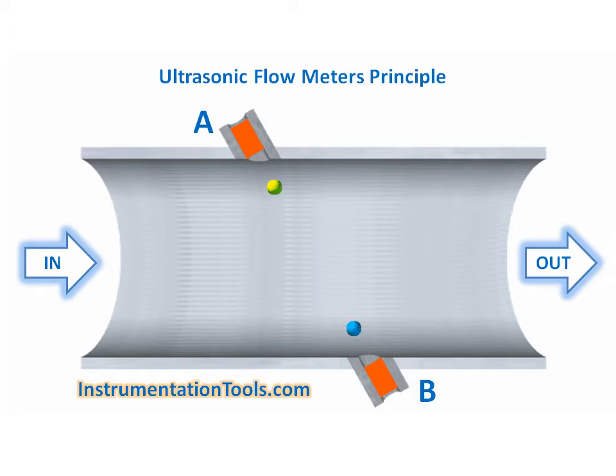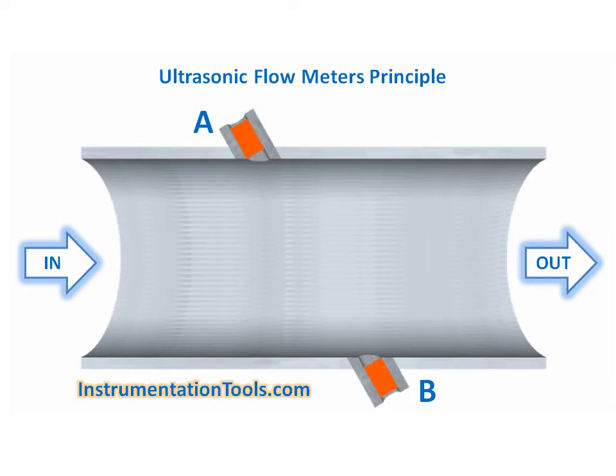Ultrasonic flow meters use sound waves to determine the velocity of a fluid flowing in a pipe. At no flow conditions, the frequencies of an ultrasonic wave transmitted into a pipe and its reflections from the fluid are the same. Under flowing conditions, the frequency of the reflected wave is different due to the Doppler effect.